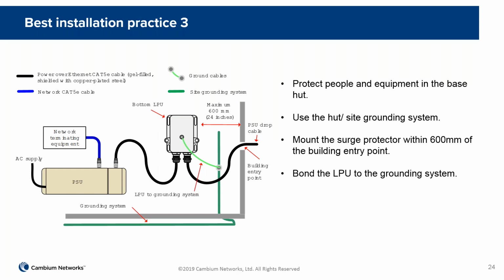So the residual voltage, as I mentioned, would be 1 to 200 volts from the surge, and whatever network equipment happens to be in the hut should be capable of tolerating that level of voltage. I've shown something which looks like a PIDU here, but an Ethernet switch, a PoE switch, would have a nominal 1 to 2 kV withstand capability. So that is the summary of the best installation practice.